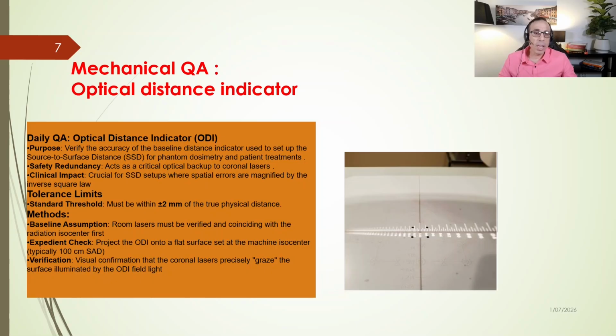Now let's review the daily QA protocol for the optical distance indicator, or ODI. As you can see in the figure, we have a ruler type scale and it can be seen on the patient skin when we are doing setup. The primary objective here is to confirm that our optical distance tracking remains accurate over time. This is a traditional but vital mechanism used daily for setting up the source to surface distance during patient treatments, especially in electron treatments. And for phantom dosimetry, for physics, we are using this optical distance indicator as a setup component. Clinically, the ODI serves as an essential safety redundancy to our coronal wall lasers.